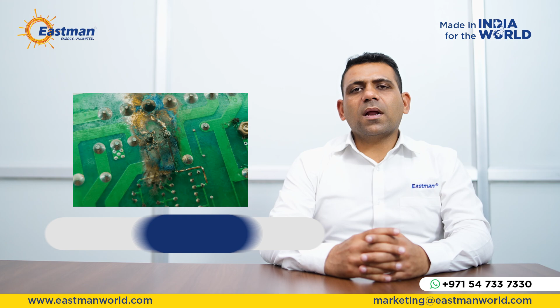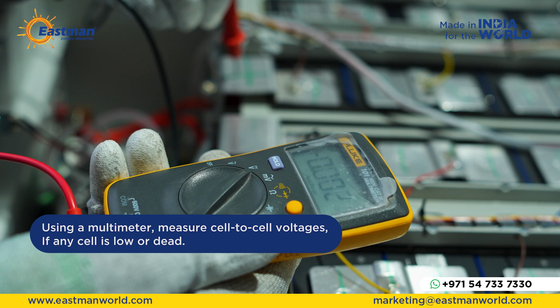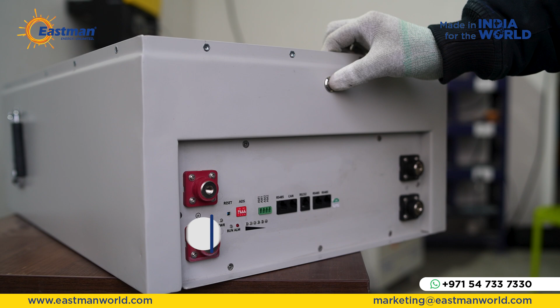Second, cell related problems. The issue with the cell voltages. Using a multimeter, measure cell to cell voltages. If any cell is low or dead, the AFE will stop responding, as a missing or loosely connected wire can trigger the fault. So voltage balancing needs to be done, and if any wrong wiring is there, it needs to be corrected. Once all is done, simply switch off the battery, wait for some time and then switch it on.